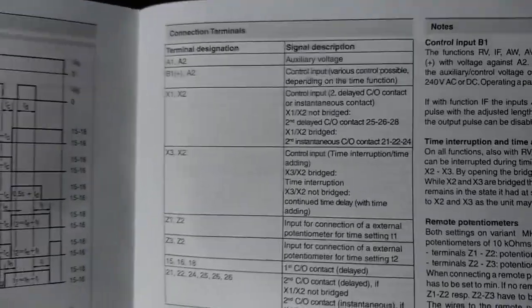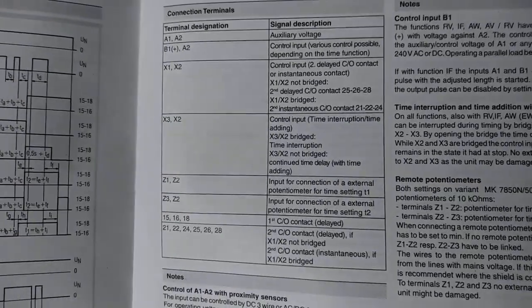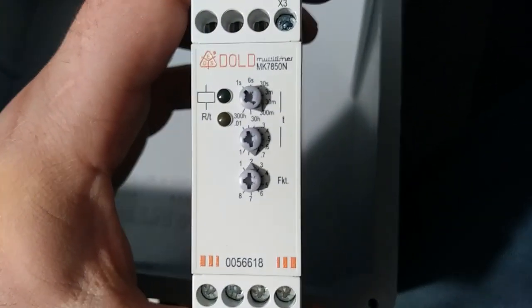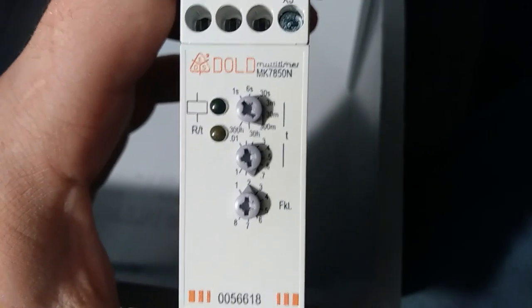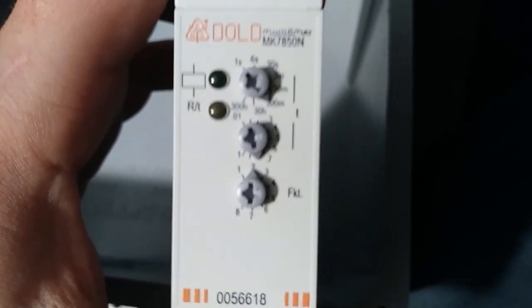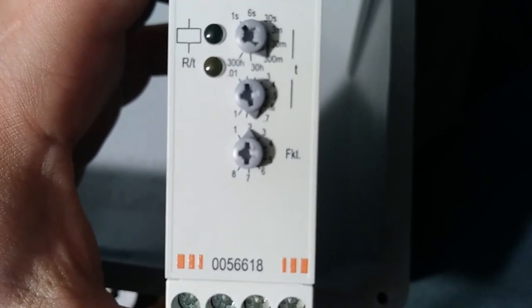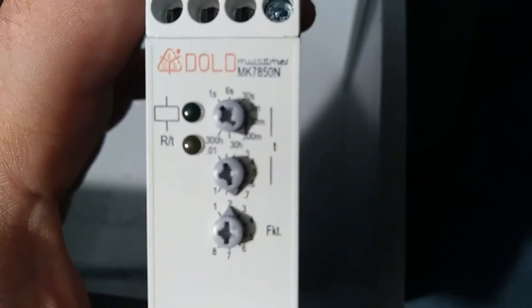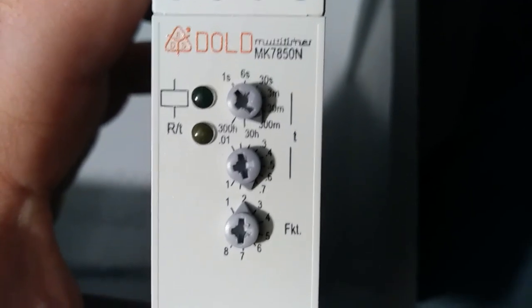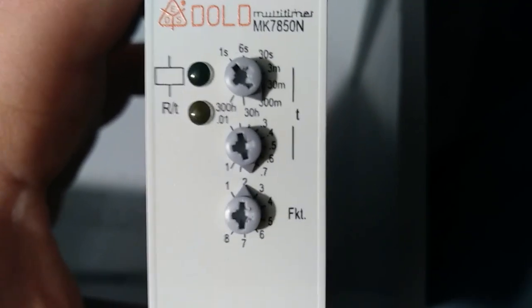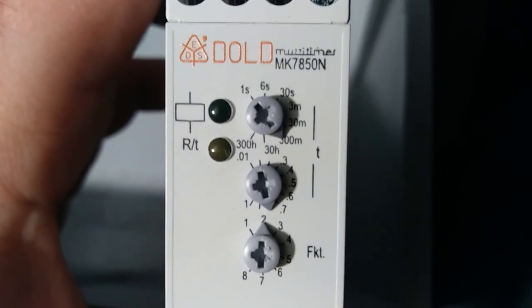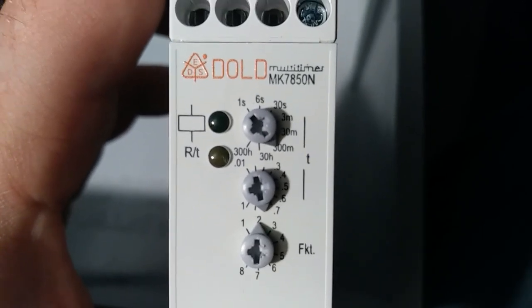And then you look over here into the terminal designations. And that's going to give us pretty much all the other information we need. Okay, so if my calculations are correct here, I set it to function switch number two, or this function switch to position number two. I set the timer to the 300 minute range. And then I am getting what I believe is 0.8 of that range by putting it there. There's a couple numbers missing from this, but it's because they don't fit.